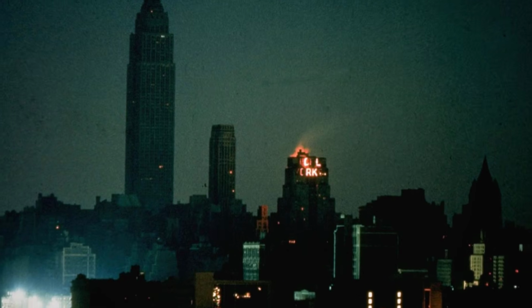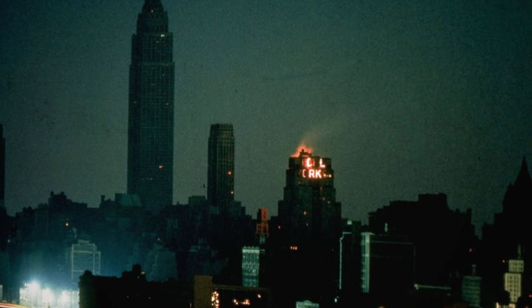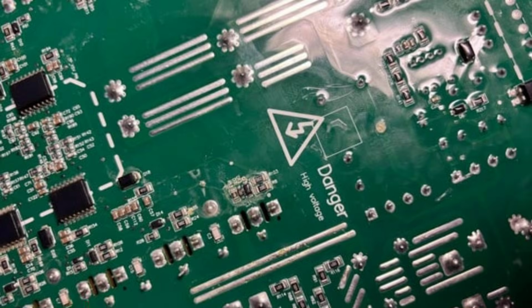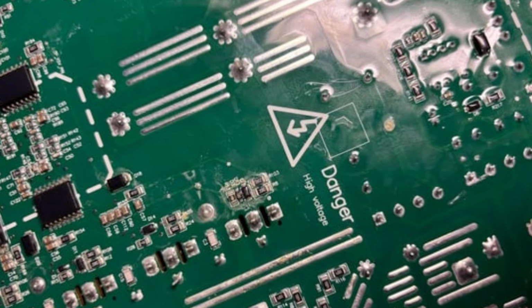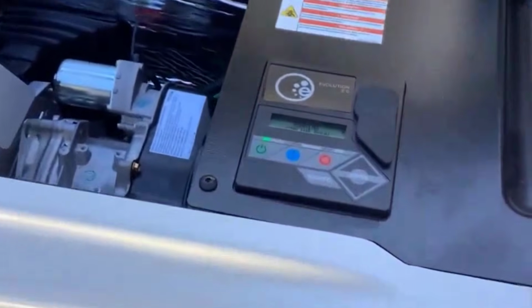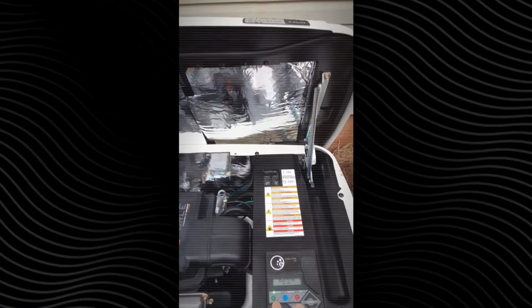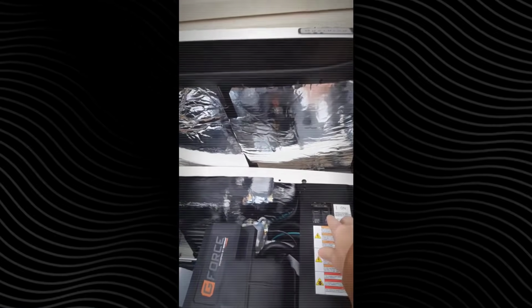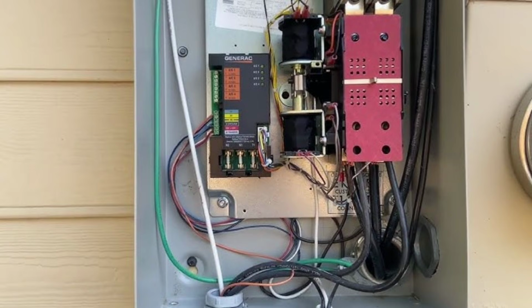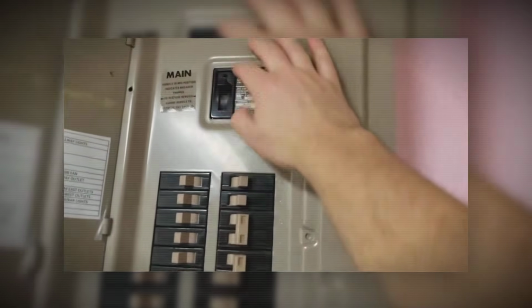This creates a deeply infuriating and dangerous situation. The grid is dead, the transfer switch computer is fried, but the generator engine outside is perfectly fine. You might even hear the engine fire up and start running, but because the automatic transfer switch is dead, it will not physically allow electricity to enter your house.